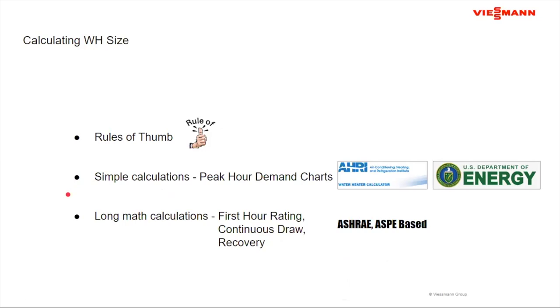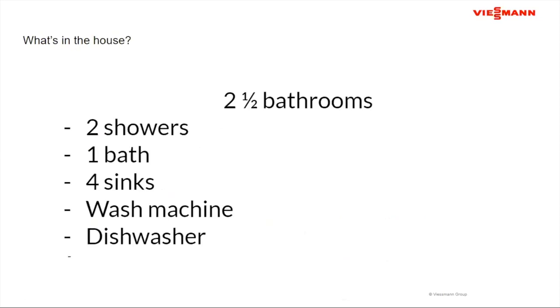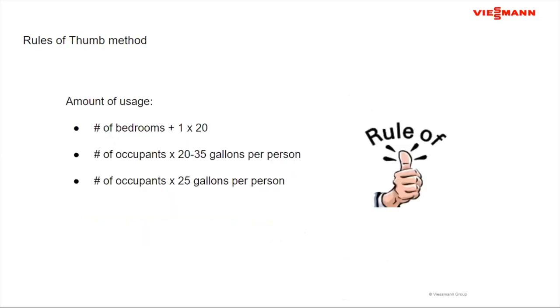I have my rule of thumb. I have my AHRI charts. I have my ASHRAE manual if I need to go long form on it. We're going to look at the first two just for today's discussion. So back to my building. 2.5 bathrooms, 2 showers, 1 sink, 1 bath, 4 sinks, a washing machine, and a dishwasher is what we're dealing with. Okay. So if I'm using my rule of thumb, usually the rule of thumb is based sometimes on bedrooms, sometimes on occupants, sometimes on bathrooms. Today, I'm just going to talk about the bedroom or the occupants.